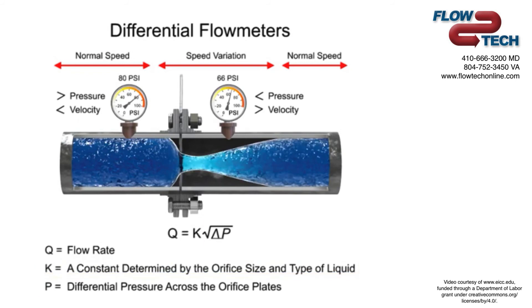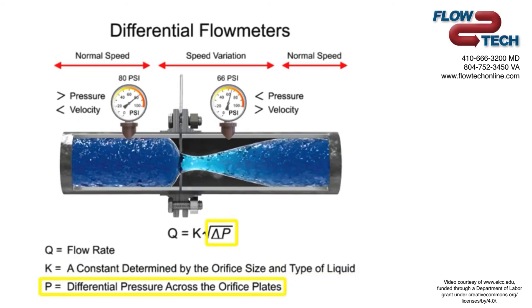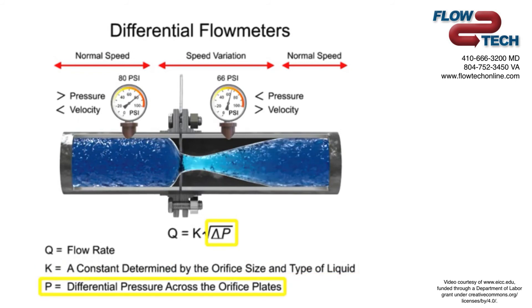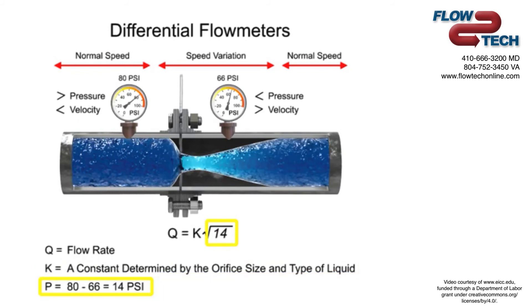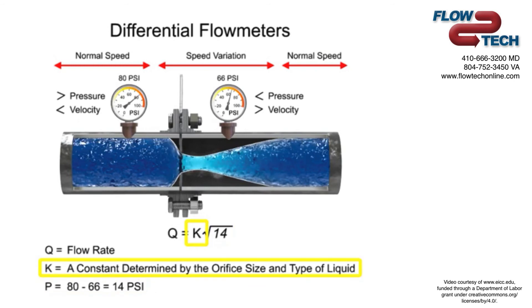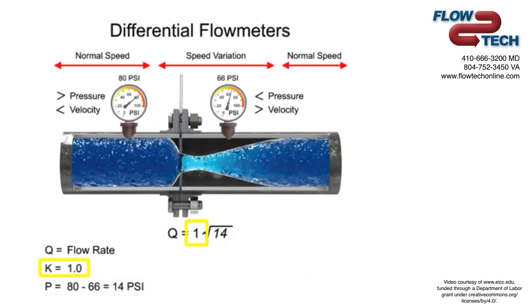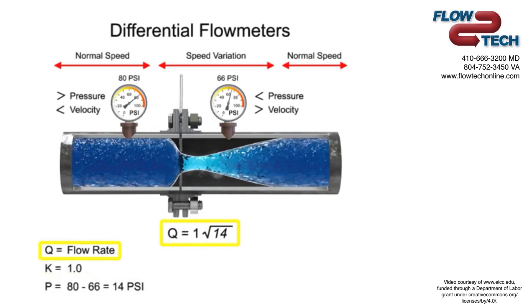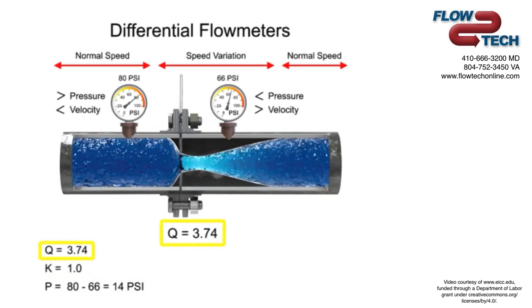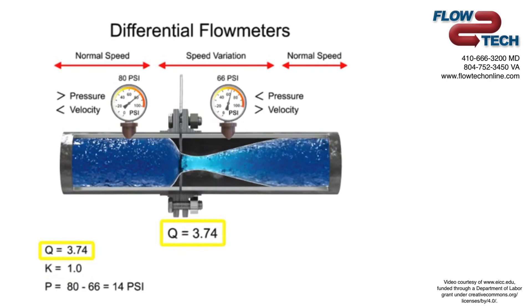For example, if the differential pressure increases by 14 PSI with a K factor of 1, the flow rate is increased by 3.74.